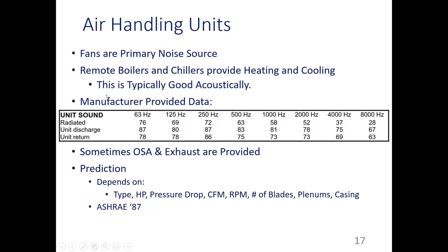So this is what manufacturer provided data usually looks like. You have radiated, which is just the fan noise that comes out through the casing of the unit. Unit discharge, also known as supply. Unit return, also known as inlet. It is not always the case, but it is pretty often that the return is going to be quieter than the supply. This is likely part of the design.